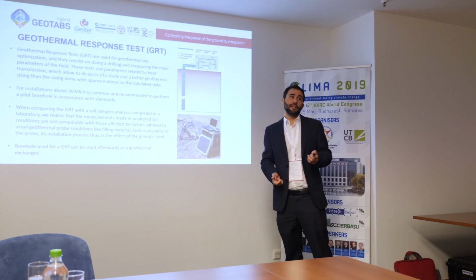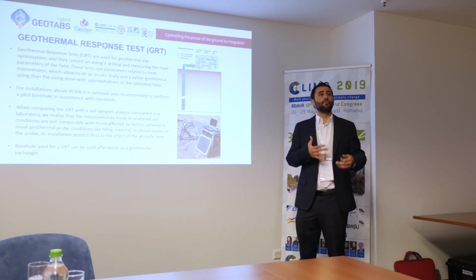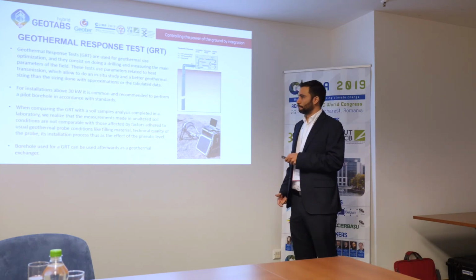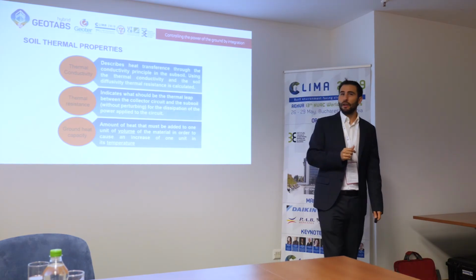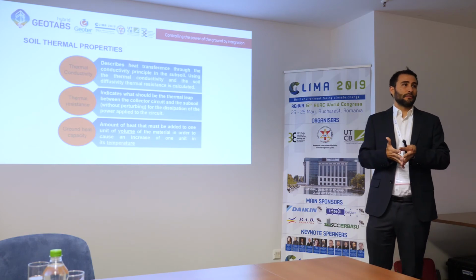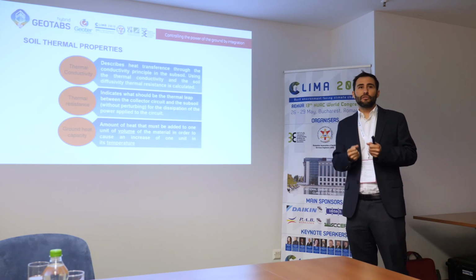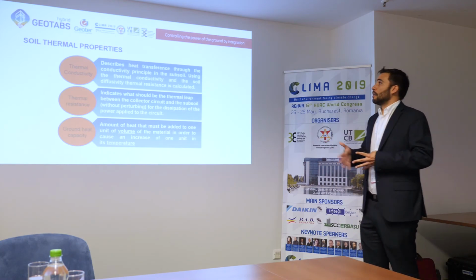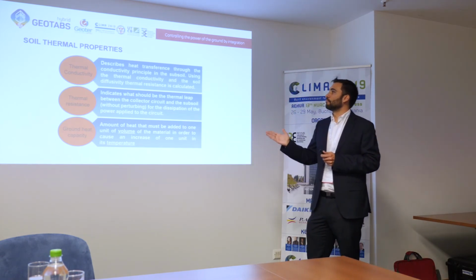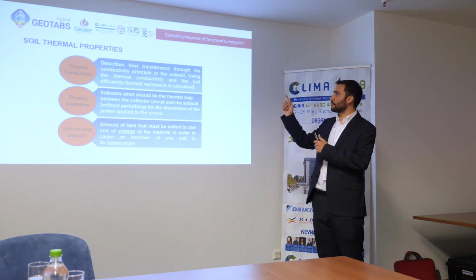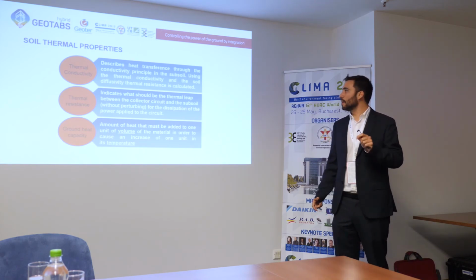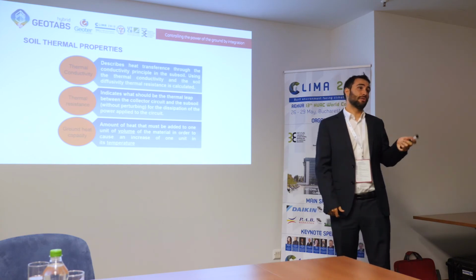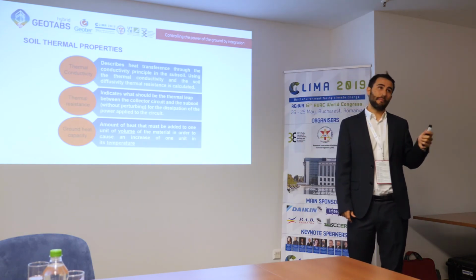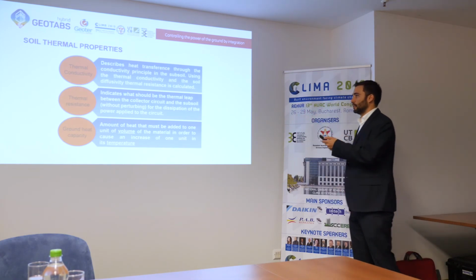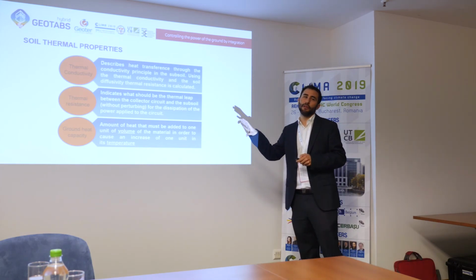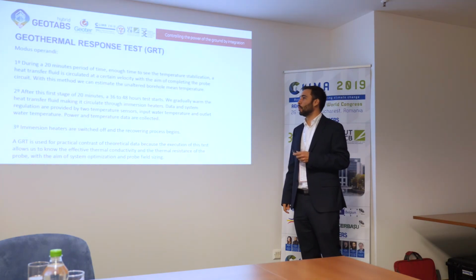With this pilot borehole, we can obtain the main parameters of the subsoil, the parameters we need to design our borehole field. These parameters are thermal conductivity, thermal resistance, and ground heat capacity. It's very important to do the test on site because we can analyze the realistic conditions on site, not in a laboratory. Thermal conductivity describes heat transference along the subsoil. Thermal resistance indicates what should be the thermal lead between the collector circuit and the subsoil for the dissipation of energy. And ground heat capacity is the amount of heat that must be added to one unit of volume to increase the temperature. With these three parameters, we can properly calculate our borehole field.